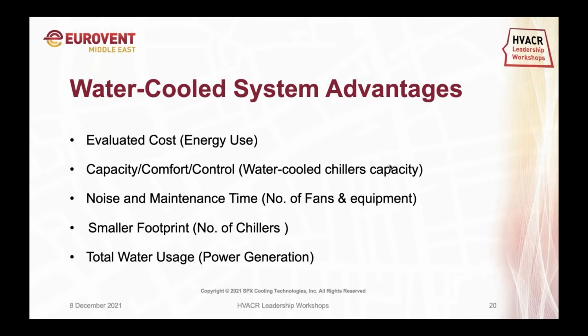Usually cooling towers and air-cooled units are installed on the roof of a building. If you compare the number of fans, cooling towers require maybe 2, 3, or 4, versus on a large capacity project you might need 6, 7, or 8 air-cooled chillers. The number of fans generates a lot of noise, which is a very important factor, along with the footprint.